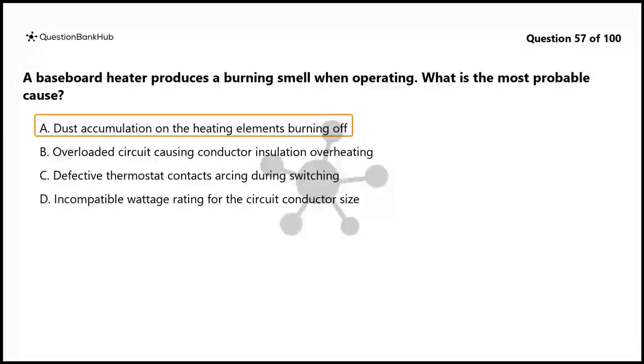The correct answer is A. Dust accumulation on the heating elements burning off. Burning smell from baseboard heaters at startup is typically caused by dust accumulation on the heating elements, especially after periods of non-use. While concerning, this is usually temporary. Persistent smell indicates investigation of connections and components.